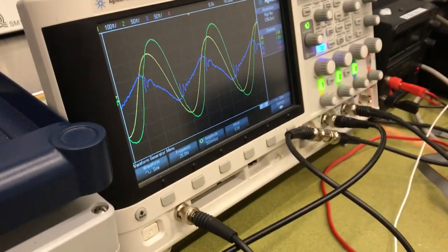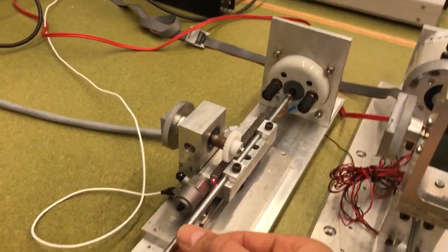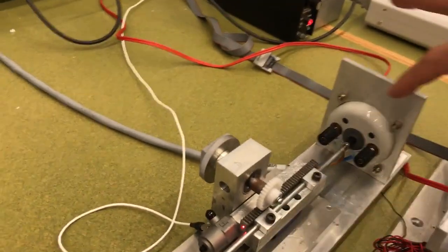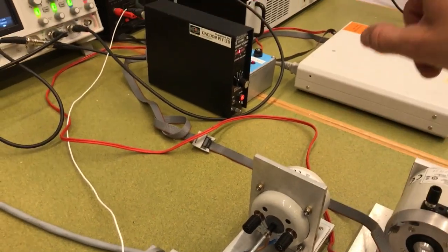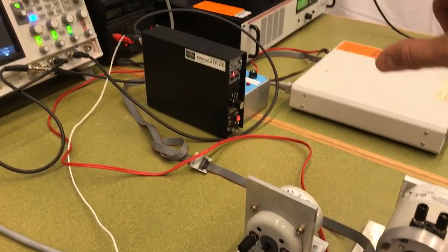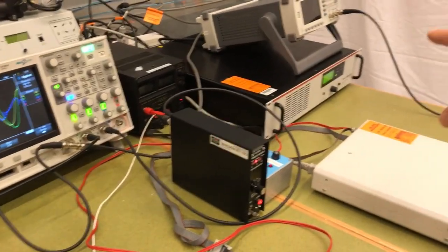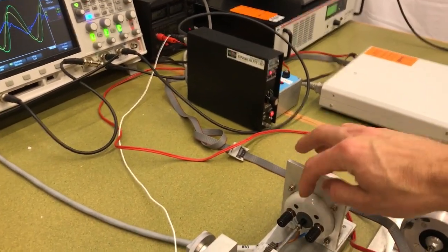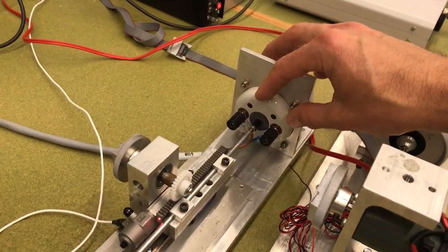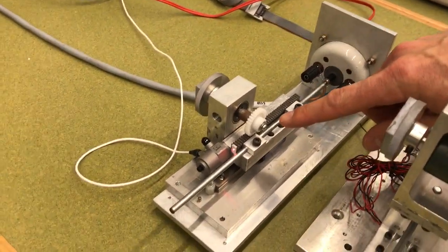You will notice that the acceleration curve is a little bit lumpy because mechanically this rig is not the best. We've got a shaker here, which even though this has been given a sinusoidal signal by the amplifier, the amplifier might already make that sinusoidal signal from the output non-sinusoidal. So there might be some squaring of that waveform by the time it gets to the shaker. The shaker is clearly a mechanical device, so that also will square the signal up.